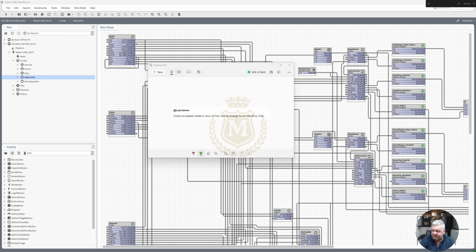Right, I've had a message today. Could you please create a video on free cooling strategy for air handling units? Right, to do this, if it's free cooling, that means that we are not using any chillers or a cooling coil. We are just using the return air temperature and the outside air temperature.